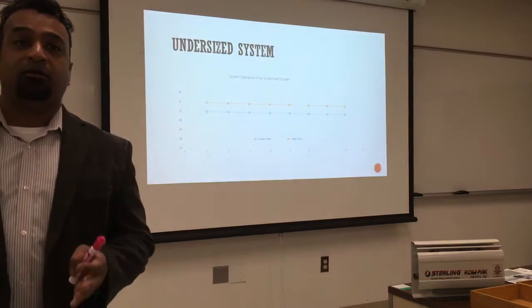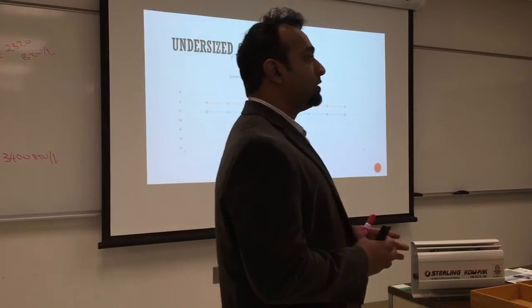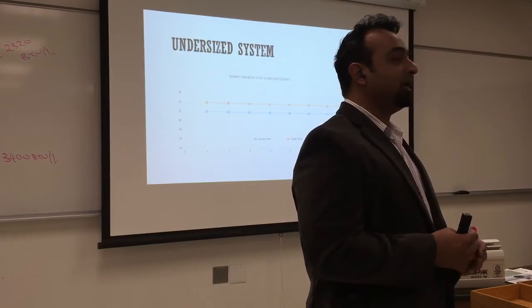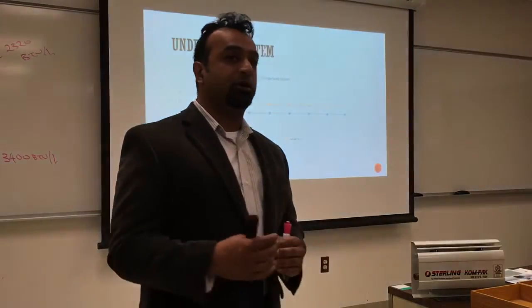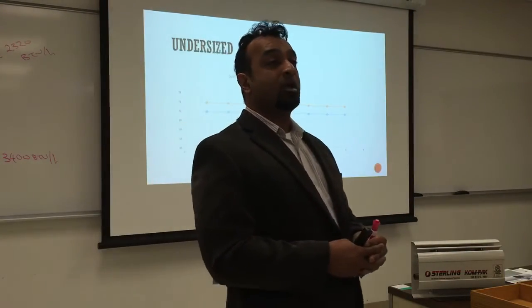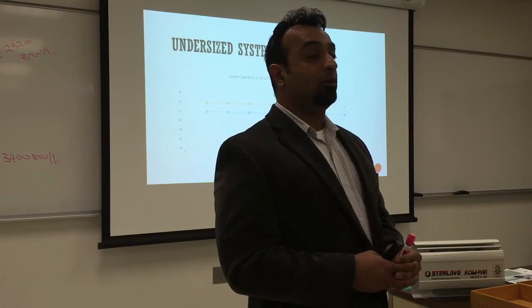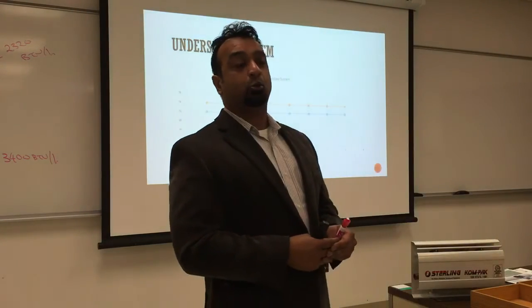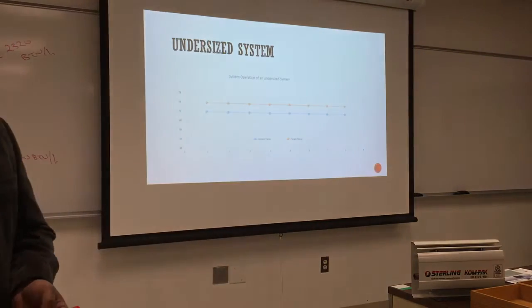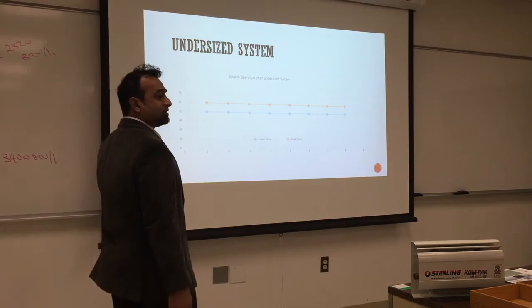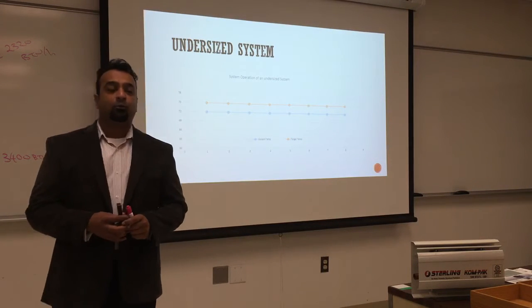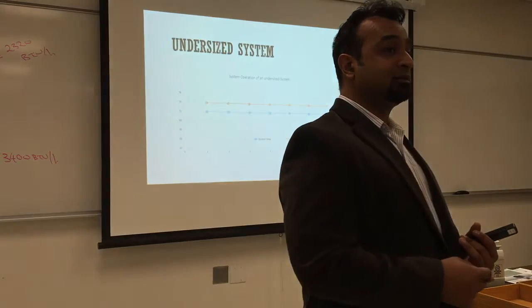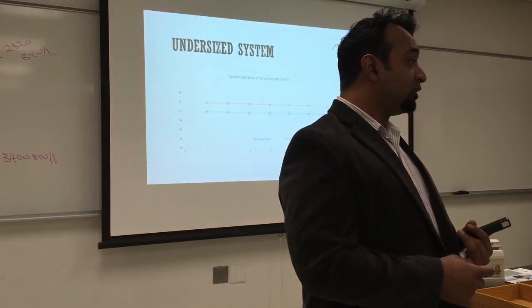This also happens if you have a system designed 10 years ago and something has been added—like a heated attic or more load—without considering the impact on the boiler. Some walls may have lost insulation value due to flooding or cracking. There are ways to improve boiler performance: maintenance is one. Sometimes the boiler drops performance because it's dirty. Also, some boilers have a temperature setting you can increase to overcompensate for lower radiator output.